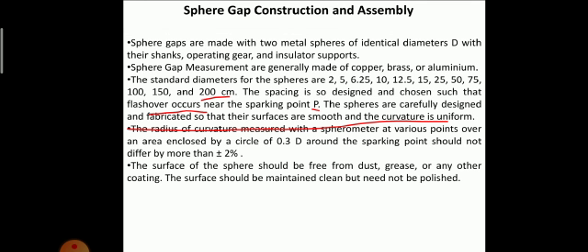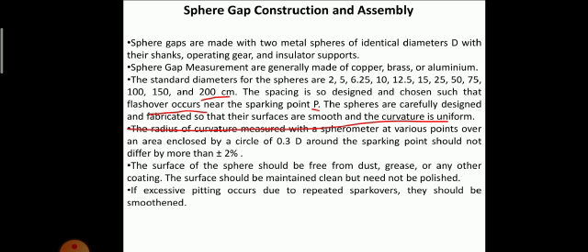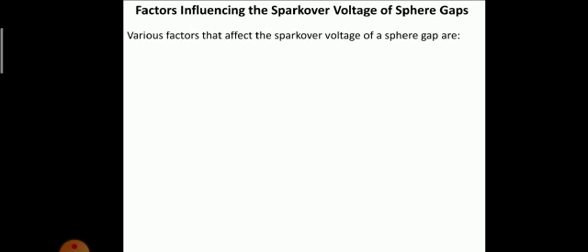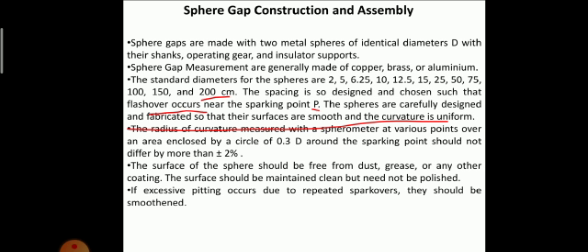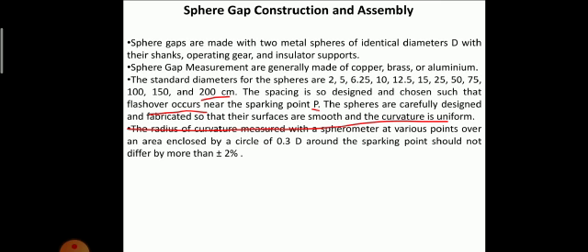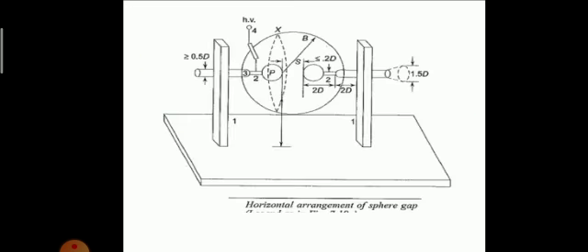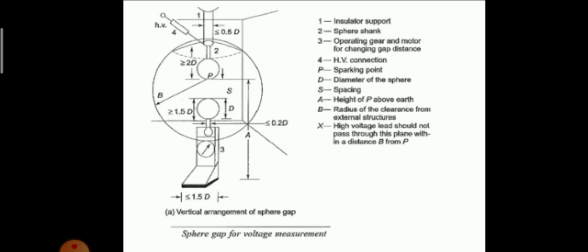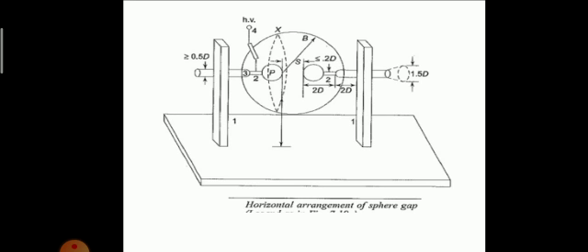The surface of the sphere should be free from dust, grease or any other coating. The surface should be maintained clean but need not be polished every time. But if excessive pitting occurs, meaning the surface is no longer smooth due to repeated flashovers or sparkovers, it should be smoothened. The dimensions of the shanks and grading rings used with the respective spheres, and what the ground clearance should be, you can see from these figures, which show the distances to be maintained and the dimensions.